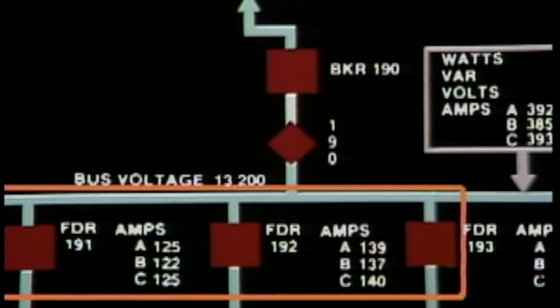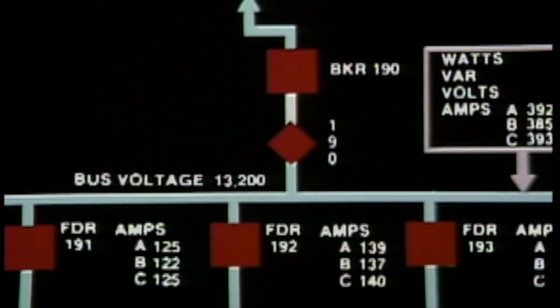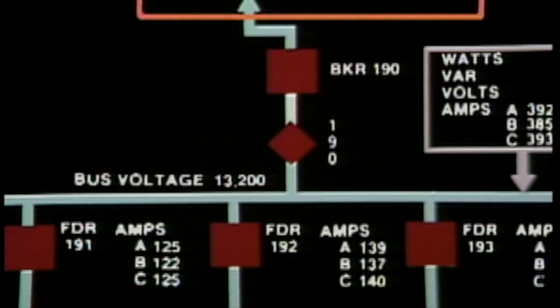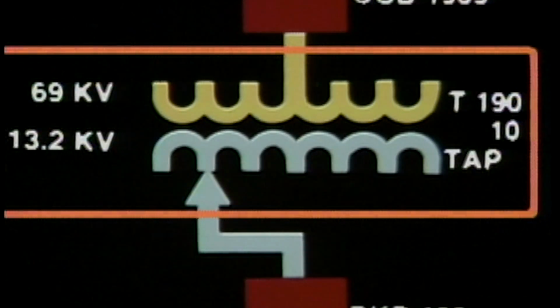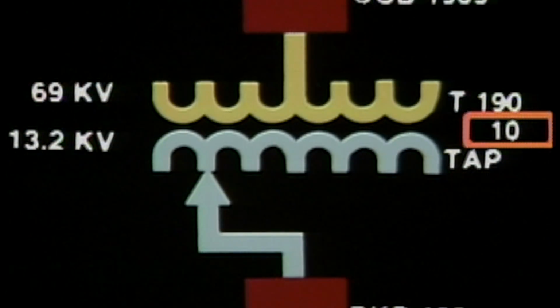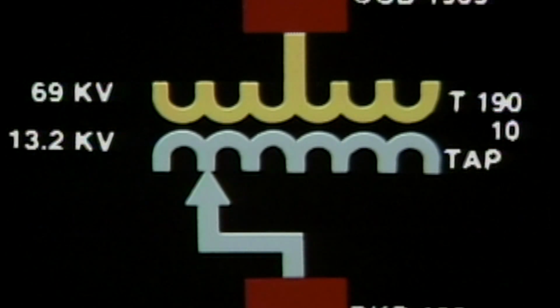Let's say that due to a temporary increase in load, these feeders need boosting from 13.2 kV to 13.6 kV. We can do this by adjusting the taps on the substation tap-changing transformer. This number, next to the tap-changing transformer, tells us that the tap is now set at tap position number 10. To boost these feeders up to 13.6 kV, we must change the taps to a higher position. In this case, the taps will move from a high number to a lower number because the taps are left of neutral on the transformer. Let's do it and see what happens.